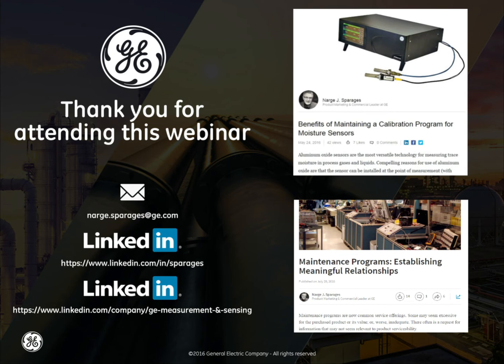So shelf life, the sensor will be fine. It can stay on the shelf in a box as long as you need it to. There's no harm, no foul. But its calibration is changing with time. Even though it's still in a box, it doesn't know that it's in an application or not in an application. As far as it knows, its application today is to measure the moisture content inside the box.